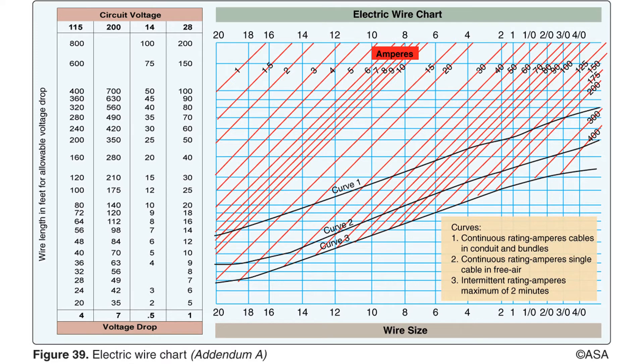In the previous example, we found the correct wire gauge for a given length of wire with a particular current flow. It did not matter whether the wire was run in a conduit or bundled with other wires, or whether it was a single wire running in free air, because the intersection point of the lines for the current and wire length were above curve 1. In this next example, we will show how to determine the correct wire gauge for a wire run in conduit when the lines for wire length and current intersect below curve 1.